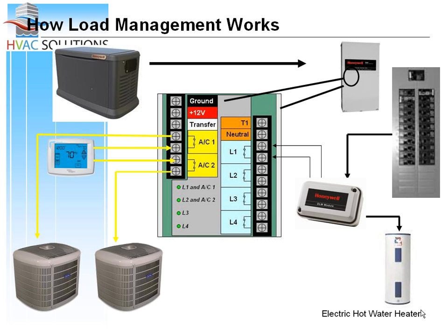From there, if there was a second air conditioner, it would go through that same process. Let's say air conditioner 2 isn't running, so it immediately goes to L2. Let's say L2 is a well pump—it would turn on provided there's enough power at the generator. Then it goes to L3, maybe an electric range or electric dryer—if that's calling and the generator has enough juice, it turns on.